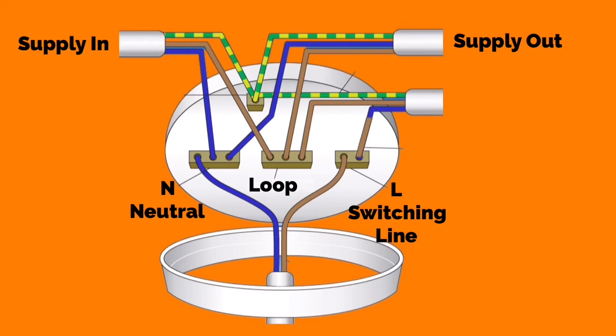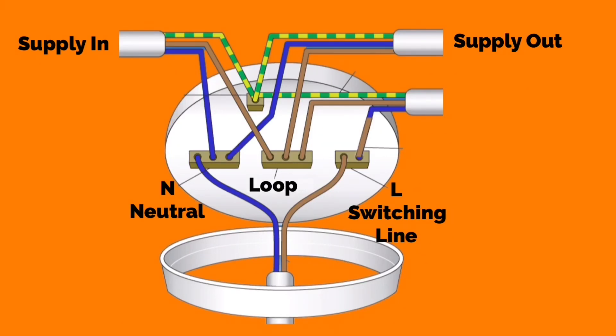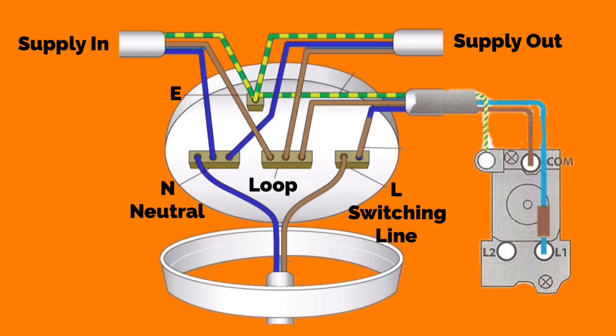If the supply comes in on the left hand side, it will bring in a permanent neutral connection terminated within the neutral block, a permanently connected line conductor connected into the loop terminal in the center, and a circuit protective conductor terminated into the earth connection within the ceiling rose itself. The bottom right hand cable is the one connected to a switch drop.